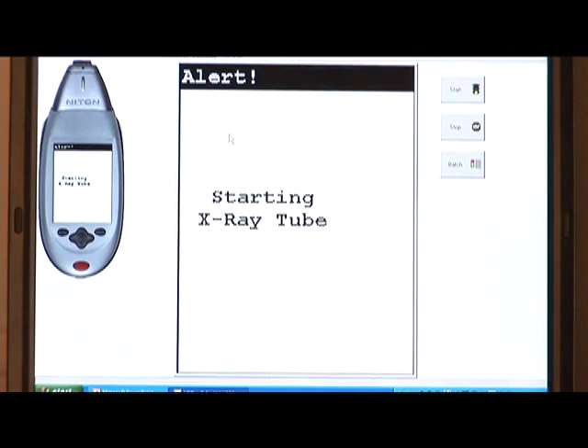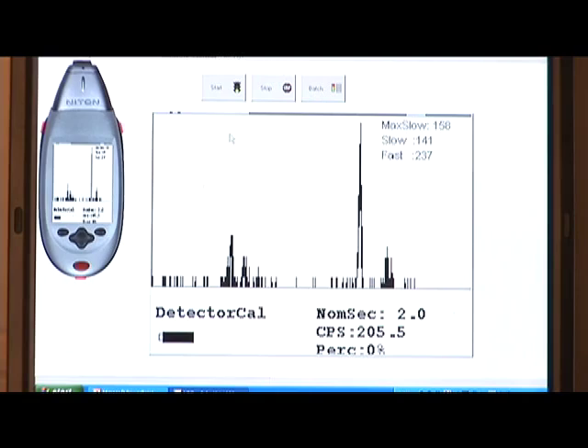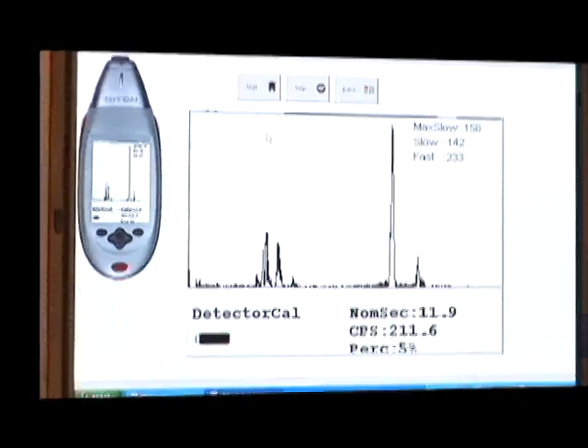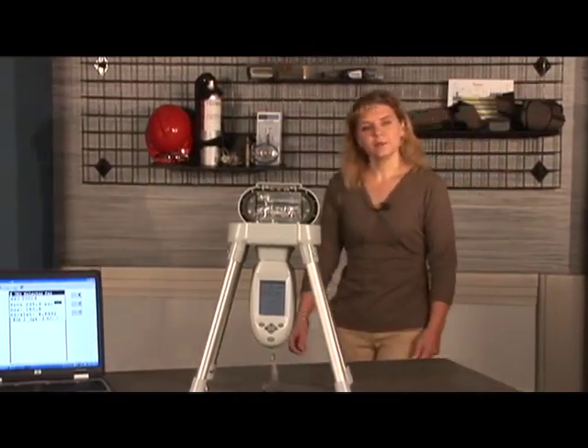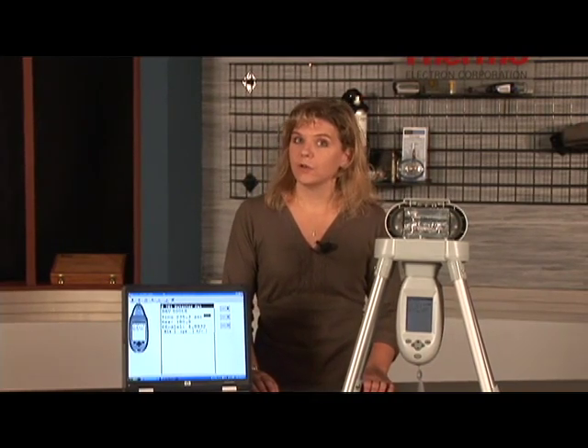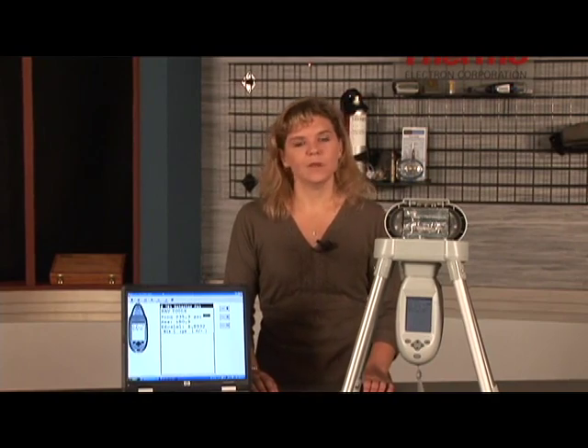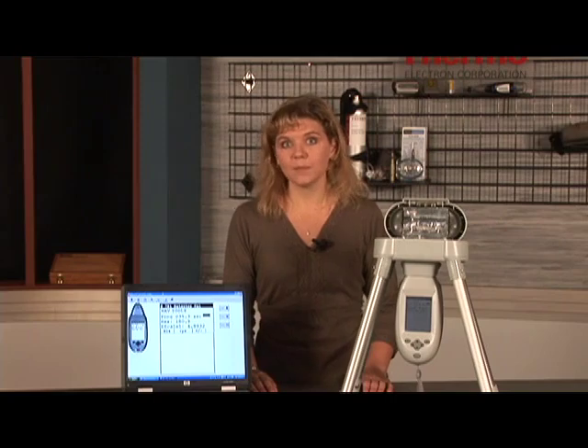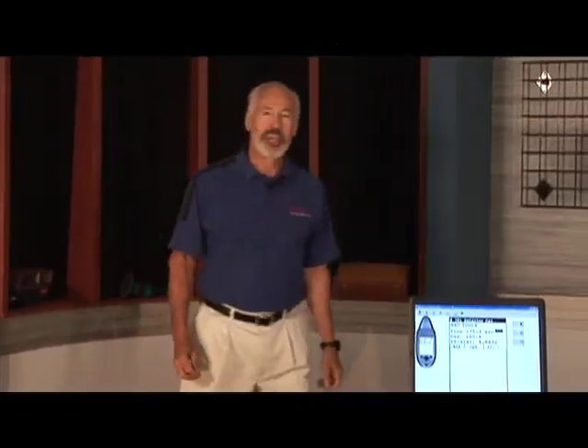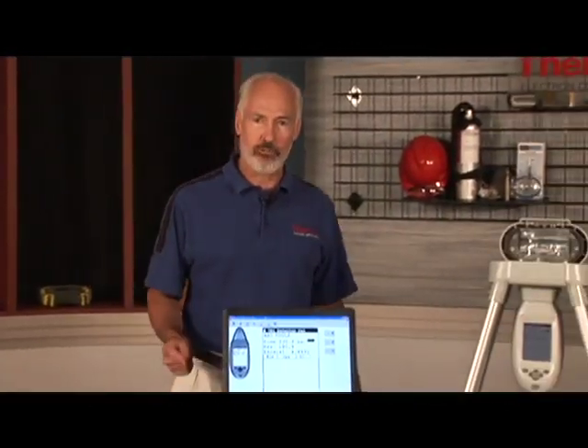This initiates an automated detector calibration update that will take at least a minute, but up to several minutes depending on your exact analyzer model and age. You may want to pause the DVD until your calibration is complete. It is important that you know not to place your instrument near a CRT monitor, like a TV or a computer, during the detector calibration process. You will also want to avoid any source of loud noise or vibration. We do recommend that you place your instrument in a quiet place so that it is not disturbed during the calibration process. During the detector calibration, the analyzer will show this screen.